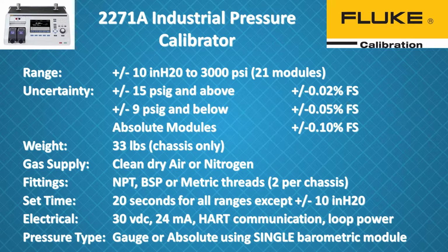Let's review some of the specifications for the 2271A. So overall, there are 21 measurement modules that can plug inside the 2271A. The lowest is plus or minus 10 inches of water. The highest is 3,000 psi. The uncertainty on these pressure modules, plus or minus 15 psig and above, is 0.02% of full scale. There are several modules between inches of water and 9 psig, which are 0.05% full scale. The absolute pressure modules are plus or minus 0.1% of full scale.